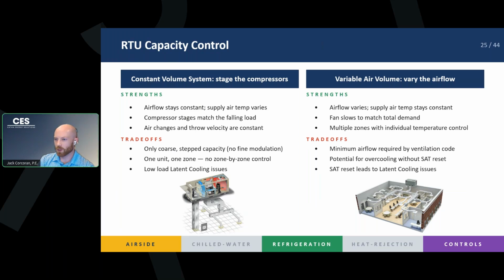In rooftop units, compressors can be staged, right? So if you have your high, medium, low settings, I guess is the easiest way to describe it. Your compressors won't be able to dial in 0 to 100%. Maybe you could just dial it to high, medium, low, and off. So you'll stage the compressor from high to low and then to off, depending on how satisfied the space temperature is. And that staging of the compressors is going to change the temperature of our air. Fewer compressors on means higher temperature air until it's off, and then it's just recirculating.